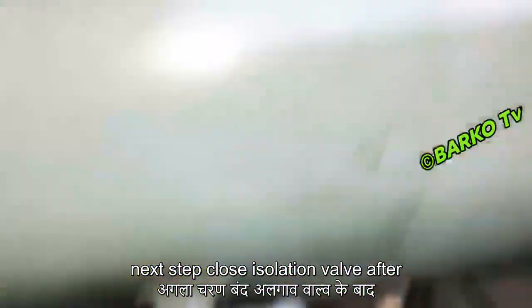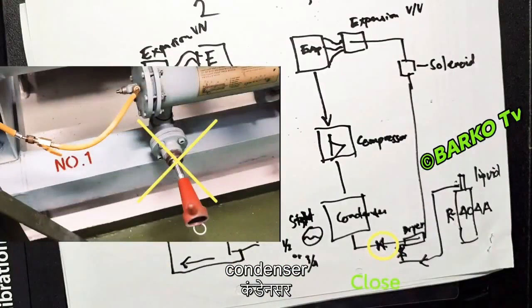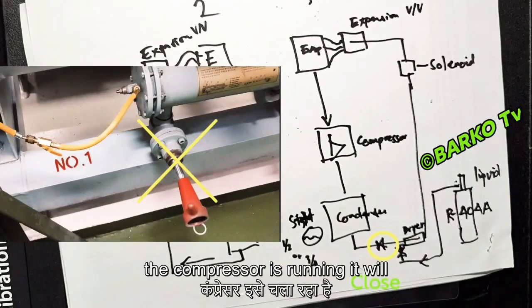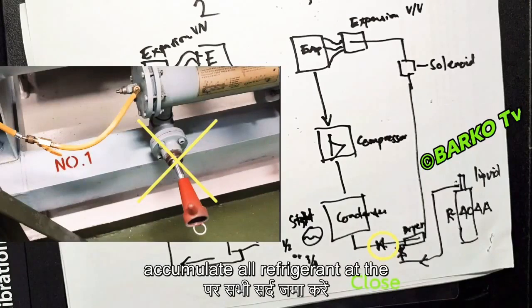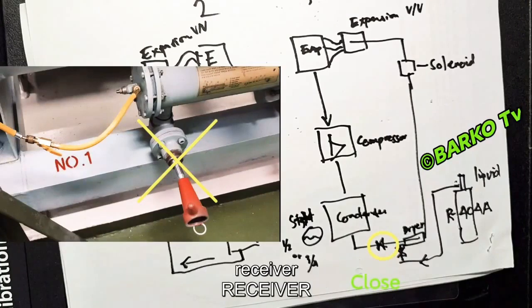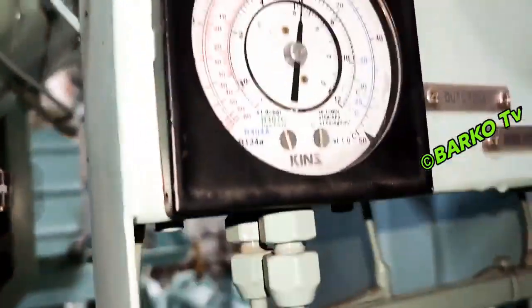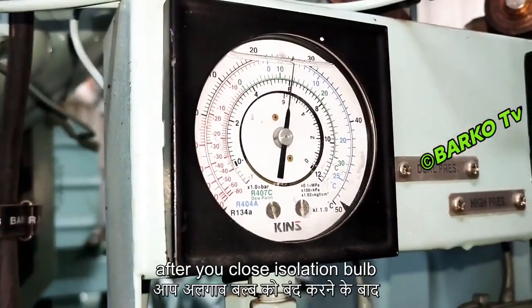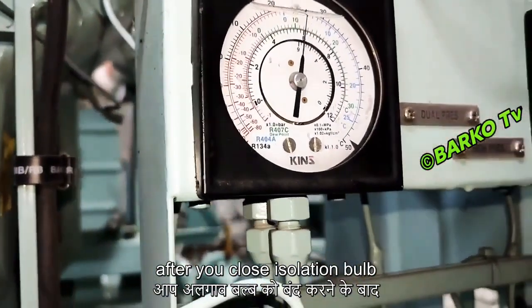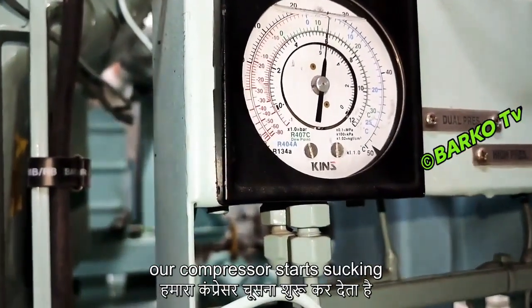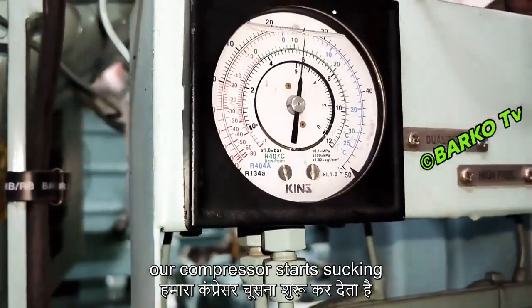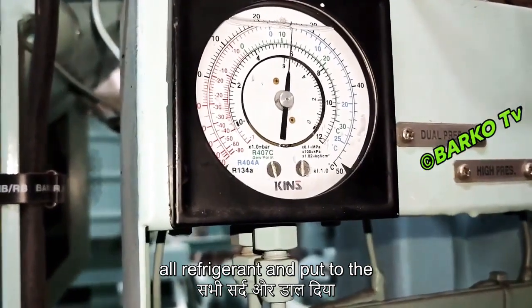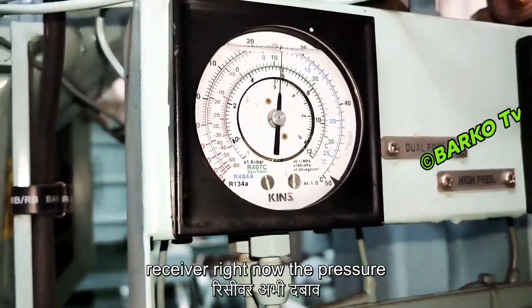Next step, close isolation valve after condenser, this one, and then the compressor is running. It will accumulate all refrigerant at the condenser / receiver. After you close isolation valve, our compressor starts sucking all refrigerant and put to the receiver.